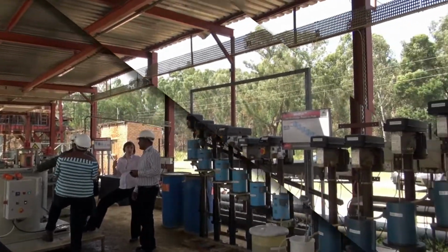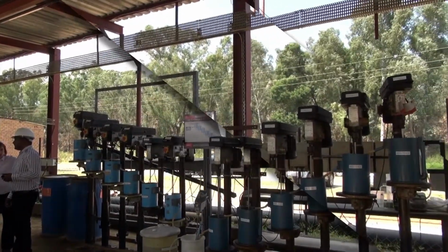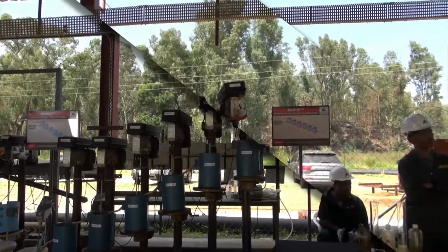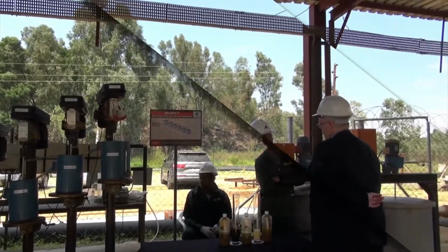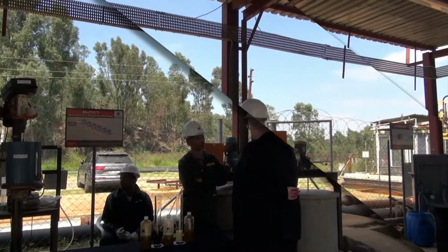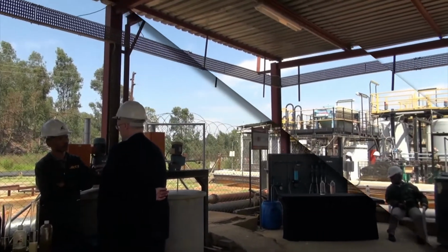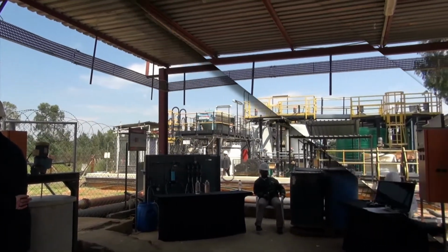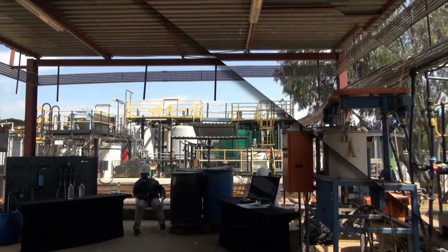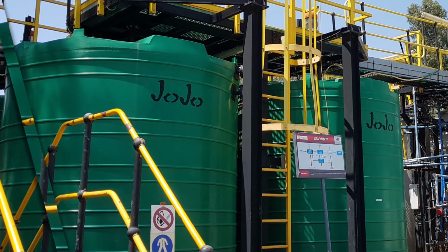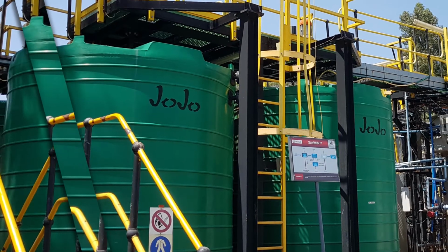Now, SAVMIN is a chemical process, precipitation based. It does not operate at high temperature, it does not operate at high pressure. And we precipitate within the first stage the metals that might be dissolved within the acid mine drainage. We remove that from the process, and then in the second step, we precipitate a big molecule called ettringite, and that then binds the sulfates from the water, and it removes most of the sulfates from the water.